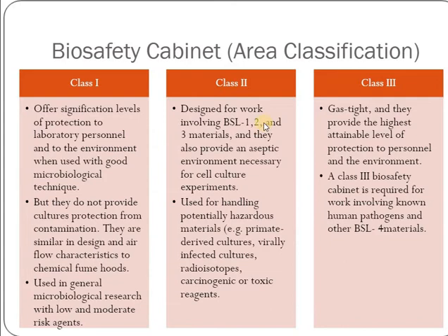The biosafety cabinets belong to three classes. The first class offers significant levels of protection to laboratory personnel and to the environment when used with good microbiological techniques. They do not provide cultures protection from contamination. They are similar in design and air flow characteristics to chemical fume hoods. They are used in general microbiological research with low and moderate risk agents.